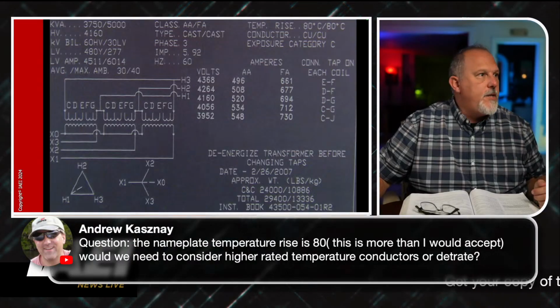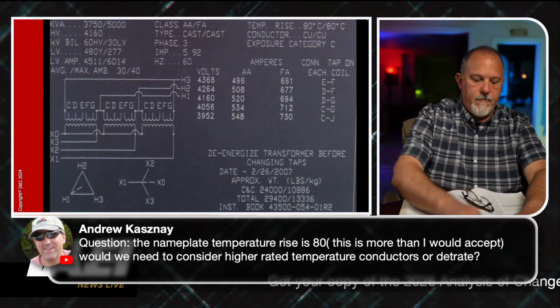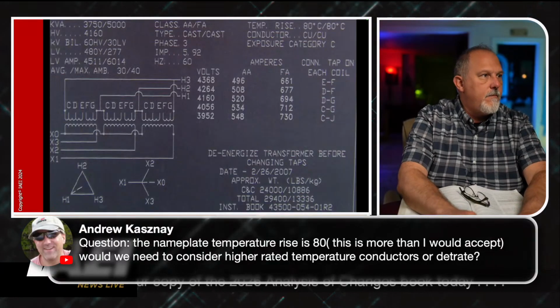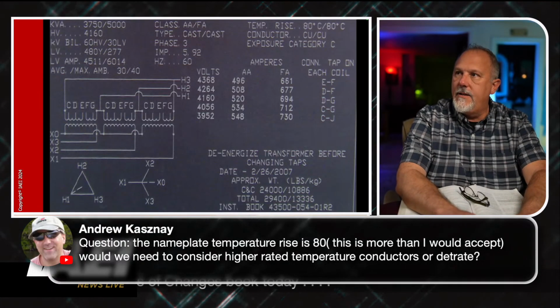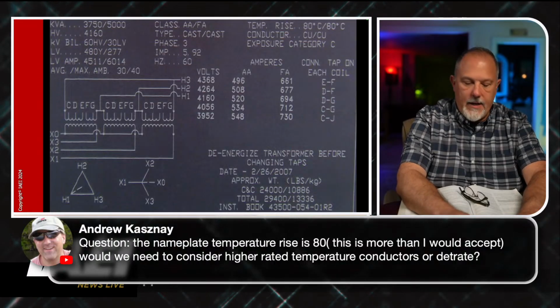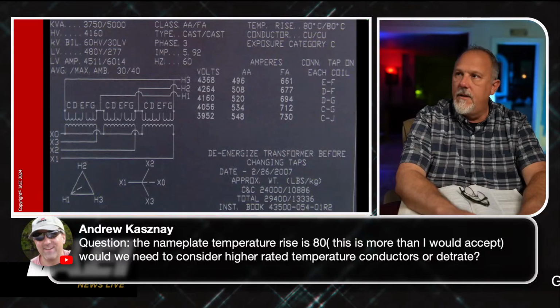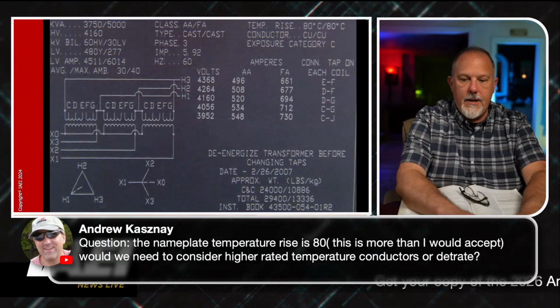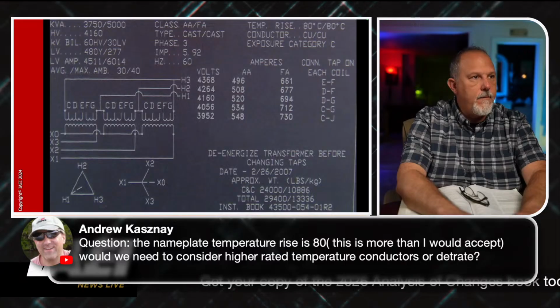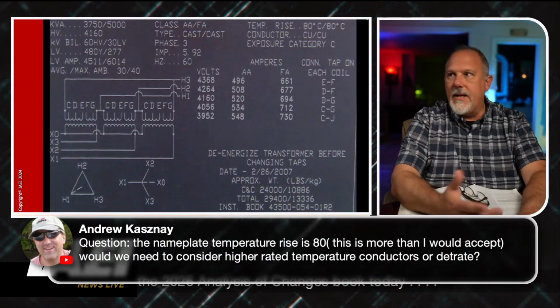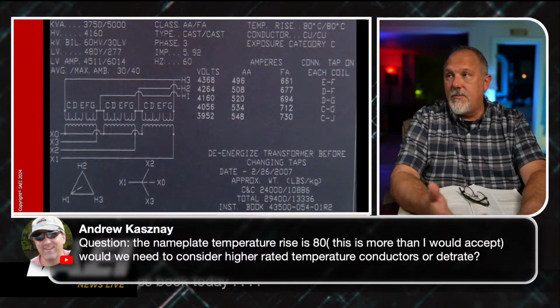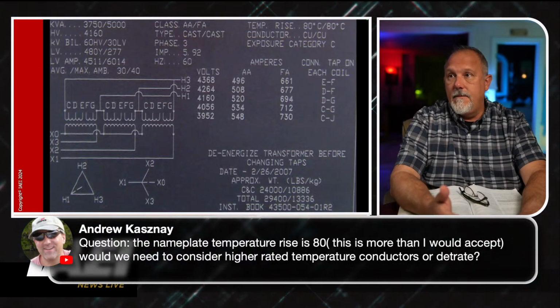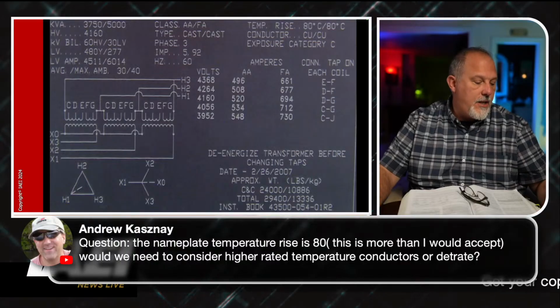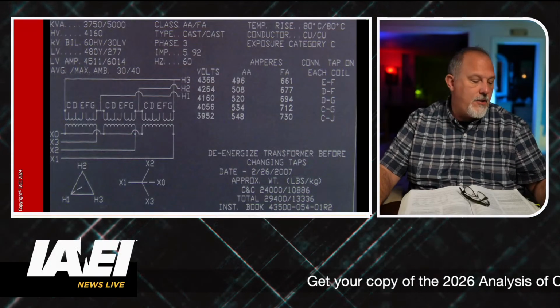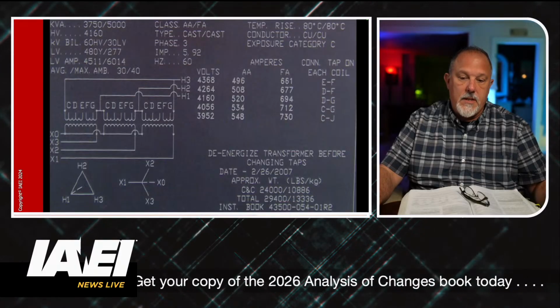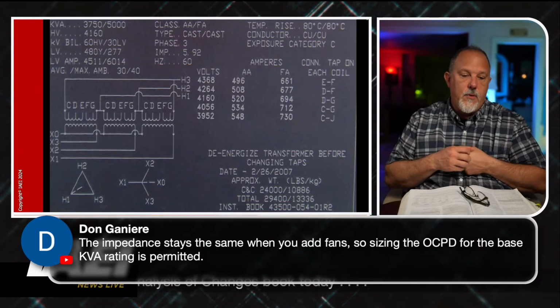Andrew, I can always rely on you for equipment that has a temperature rise of 80 degrees C. Would we need a higher rated conductor? I mean, we've got 90 degrees C insulation. Temperature rise is 80 degrees C. I don't think you would have to change that. I don't think you would have to do anything special there, Andrew, but I'm not going to say you don't, because I've got to do some homework there.